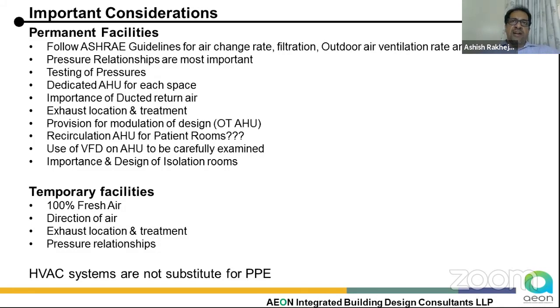The importance of ducted return air systems has been emphasized here. Again, trying to compress the floor-to-floor heights just to get more floors, getting around the NBC provision of a height limitation. I think it has come out that there are no shortcuts to ducted return air systems, especially in the critical care units and these areas. How we locate the exhaust, how we treat the exhaust air is again a consideration. At the highest point, are we letting it out, or are we treating the exhaust air, needs to be seen.